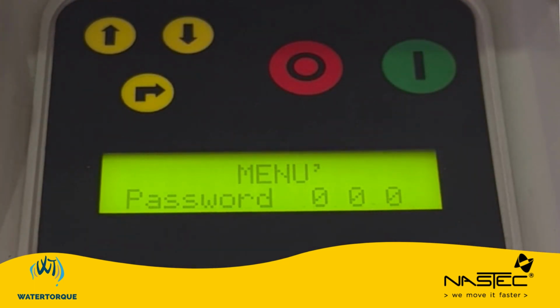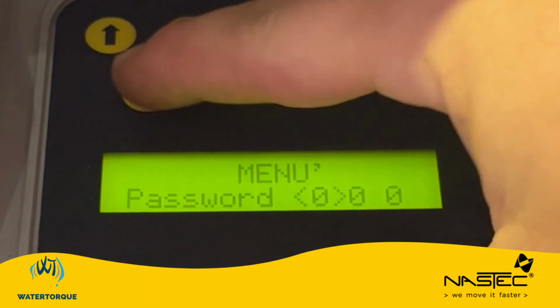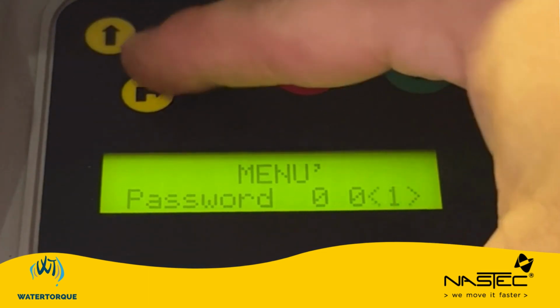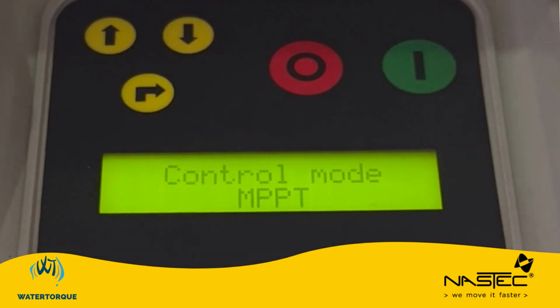The password to access the settings is 001. So we hit enter, enter, up, and then enter. Now we're into the settings of this particular pump. Out of the box, if it's a Nastec 4HS MultiPower, generally the CM module will already be set to MPPT control mode, which is maximum power point tracking.